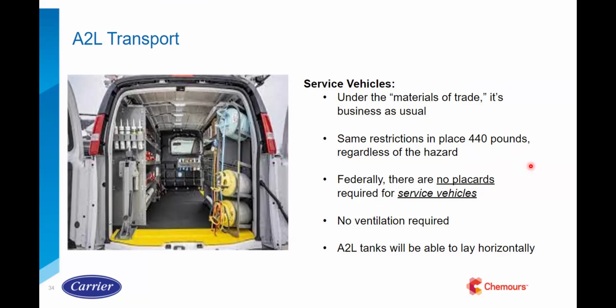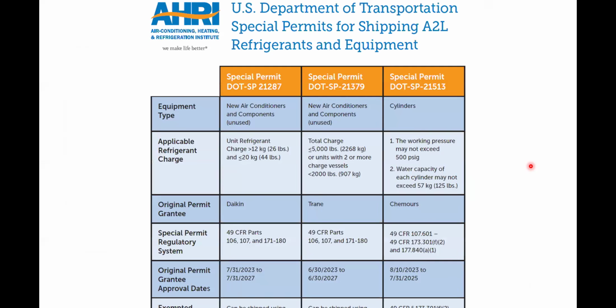A 5-ton unit's never going to have more than 26 pounds in it. So you're good. You're no problem there. But if you had a bigger vehicle, you would not be able to have any single piece of equipment with more than 26 pounds of refrigerant in it. If you need to go higher than these things, because obviously there's equipment that's transported with more than 26 pounds, I mean, not a service van, but on other vehicles, you have to get a permit from the U.S. Department of Transportation. The good news, not that getting permits is ever good news, is that if somebody else has already pulled a special permit, you don't have to rewrite your permit from scratch. You can just use their permit, right?